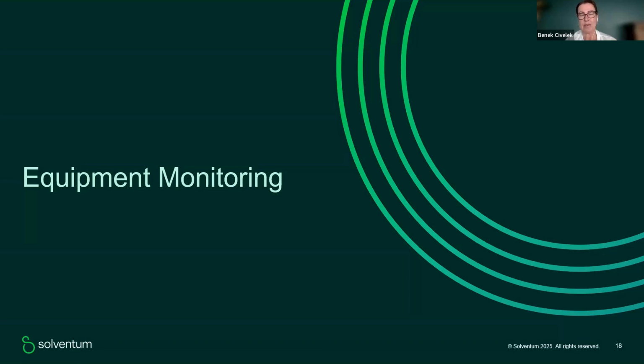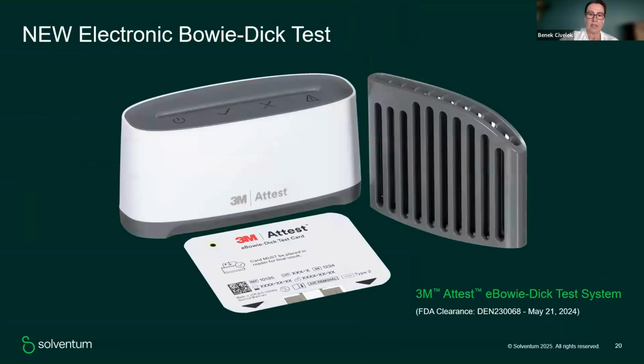Knowing about this, we have been working on a newer technology, which is all about a digital solution. It fulfills all the requirements of a test pack, because there's a certain standard, ISO 11140-4 and 5. These are all related to Bowie-Dick test ready-to-use packs. So the digital offer we are now bringing you is the new electronic Bowie-Dick test, again fulfilling the same requirements as a traditional test pack, because the same tests are performed.